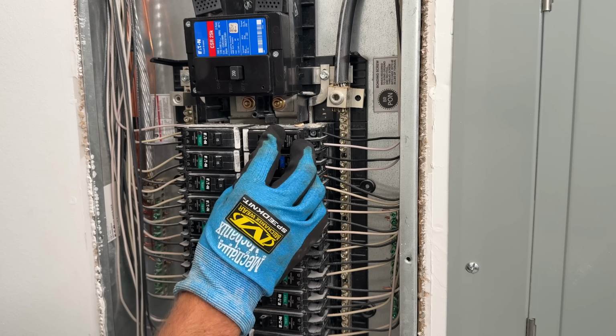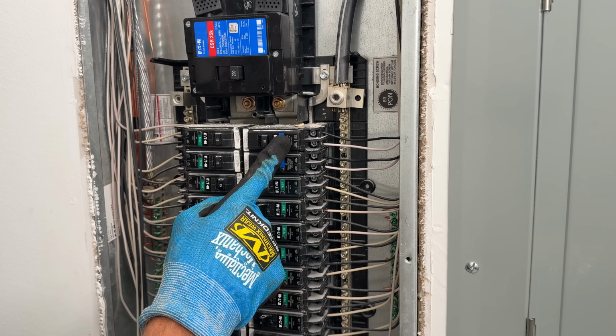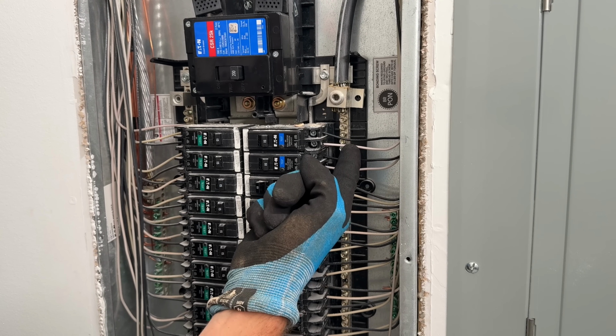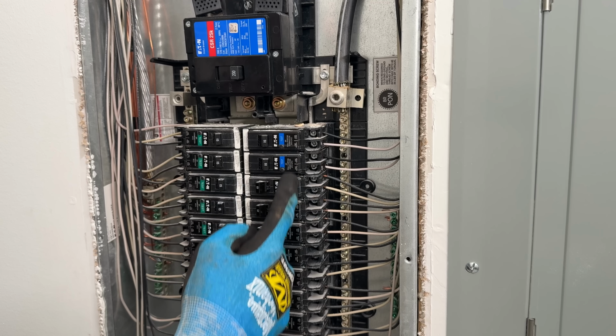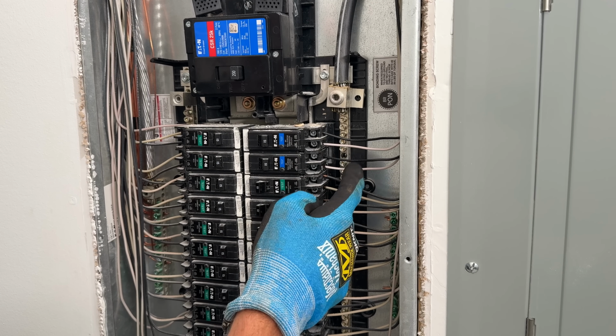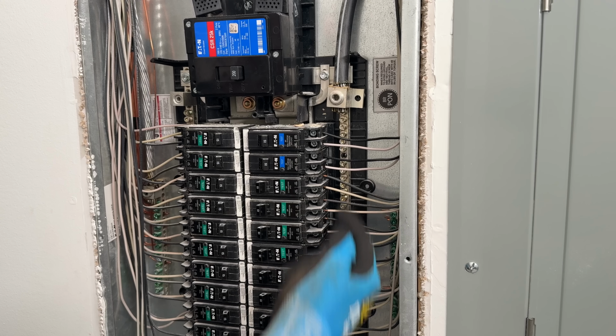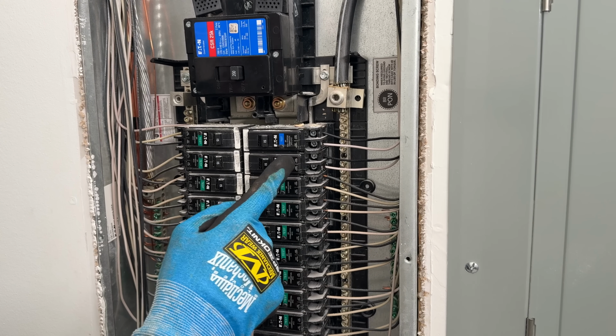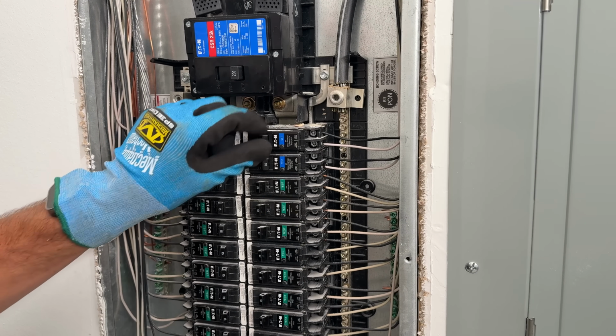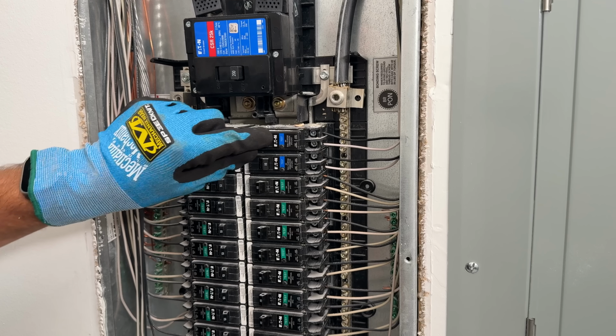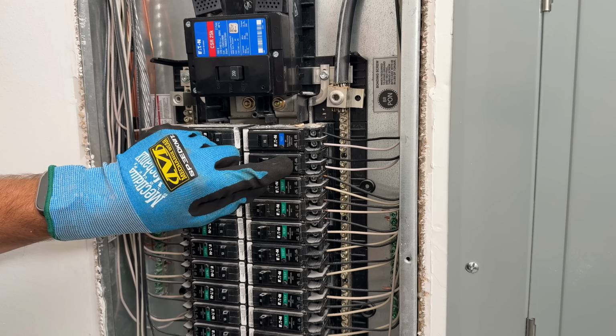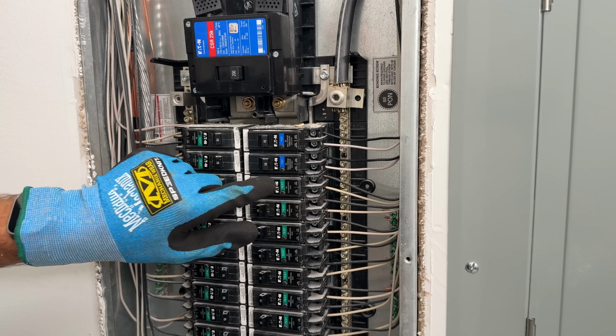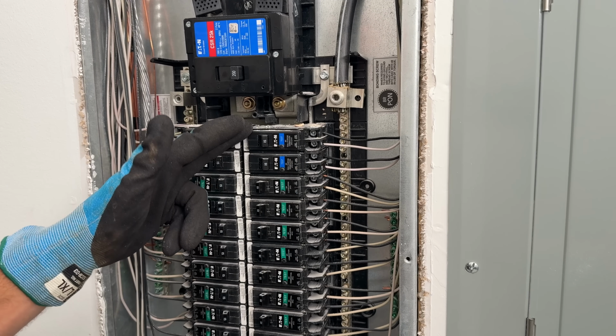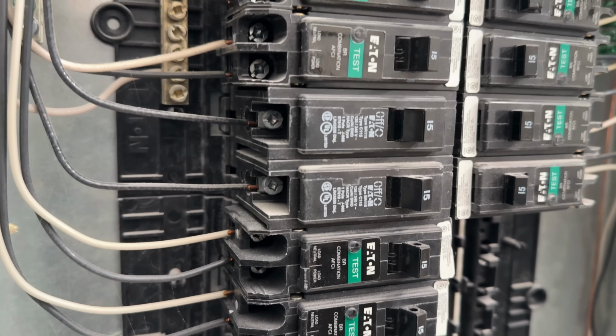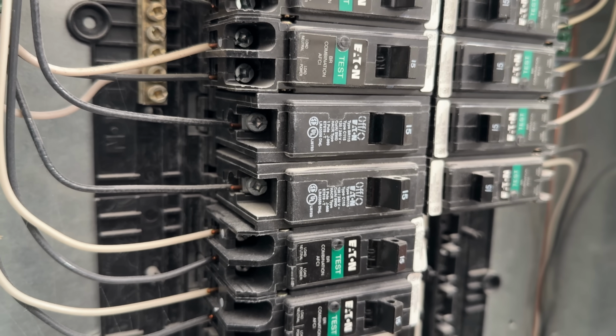So here are the 2 breakers that we're going to be moving. And just know, if you're not seeing the white neutral come into each one of your breakers, maybe you're just seeing your neutrals come into the screw terminal bus bars here, that just means you probably have a standard breaker. These specifically, these blue ones here, are dual purpose AFCI and GFCI, and then these green ones are AFCI. Without that neutral, you probably just have a standard breaker more like this one, which just is not going to have the ground fault protection.